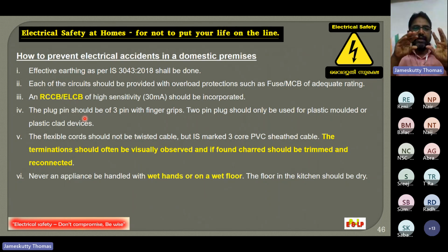Actually, a 3-pin plug will be used for equipment with a metal body. If it does not have a metal body, a 2-pin plug is enough. That is written here: a 2-pin plug should only be used for plastic moulded or plastic clad devices. That means there is no need for metal connected to earth. Now the flexible cord should not be twisted cable, but IS marked 3-core PVC sheathed cable. The terminations should be visually observed often, and if found charred or damaged, should be trimmed and reconnected.